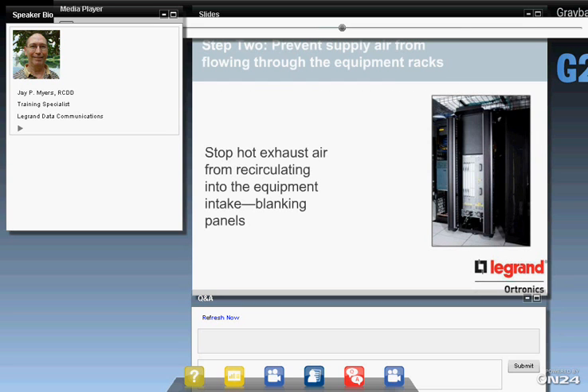We also don't want air flowing through the racks. If the hot air can flow through the empty space in the rack, that dilutes that cold air. So for this, we just need simple blanking panels, as you can see there above that switch. We want this row of racks here to be a solid wall all the way across.